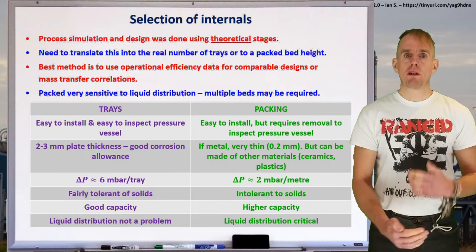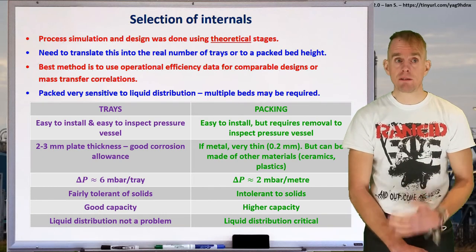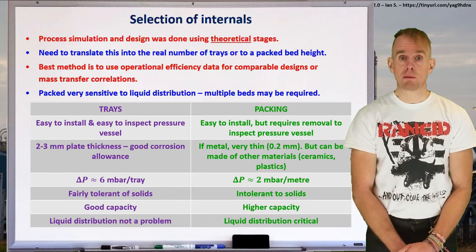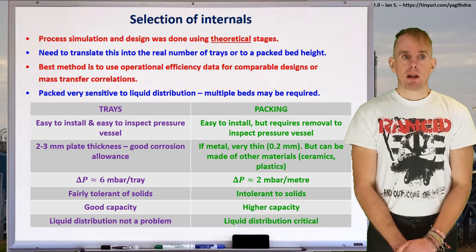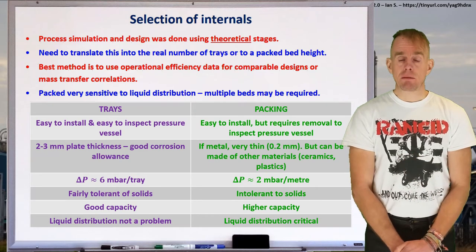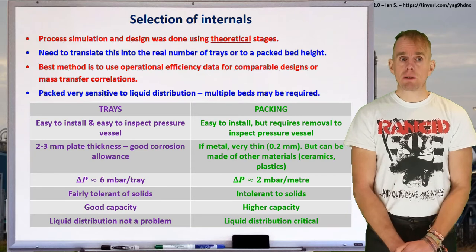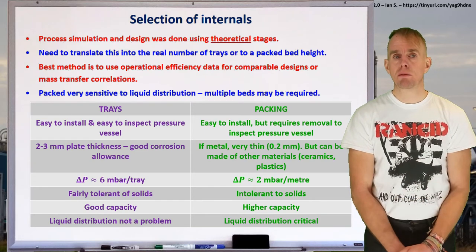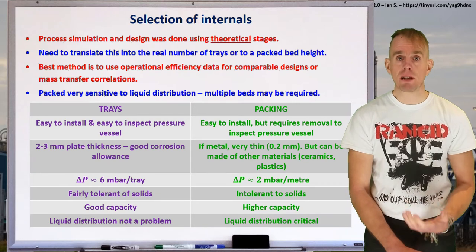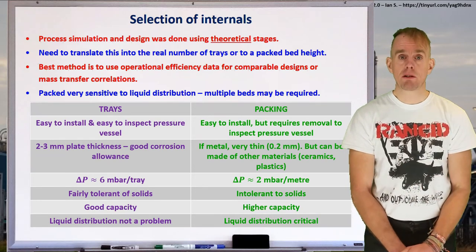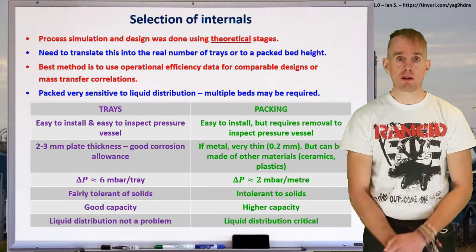Let's think about the pros and cons of each type of column internal, starting with trays. Trays are a very long-established technology. They're easy to install, and it's very easy to inspect the pressure vessel — you've got the tray and you can see the column walls. You've got good corrosion allowance, typically two to three millimetre steel plate. In terms of pressure drop, you're looking at about six millibar per tray. Trays are pretty tolerant of solids, have good liquid capacity, and liquid distribution doesn't figure as a problem. Refining experts love tray systems because they're robust, reliable, industry-tested, and just get on and do the job for 40 years.